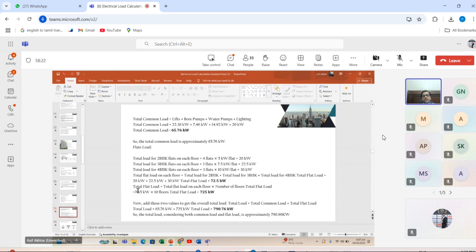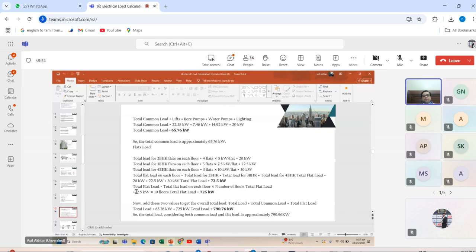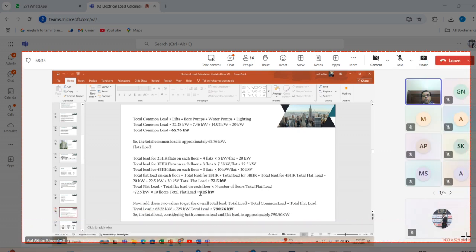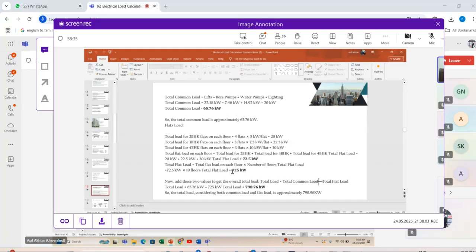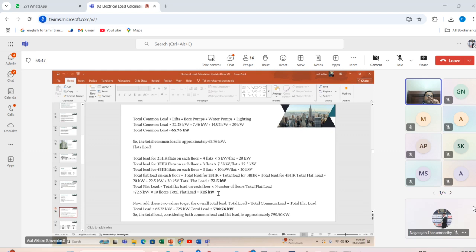Now total flat load is the total flat load in each floor multiplied by the number of floors. The number of floors we have is 10. So the total load of the flats is 725 kilowatts, 725 kilowatts for 100 flats. In this calculation, we have concluded that if we have 100 flats, our load is approximately 725 kilowatts.